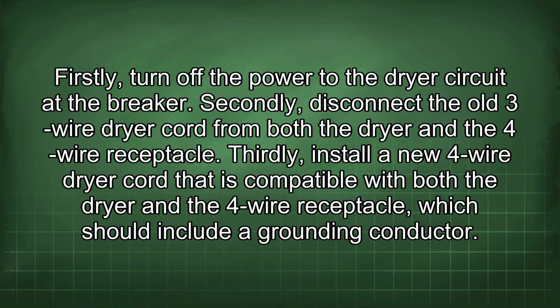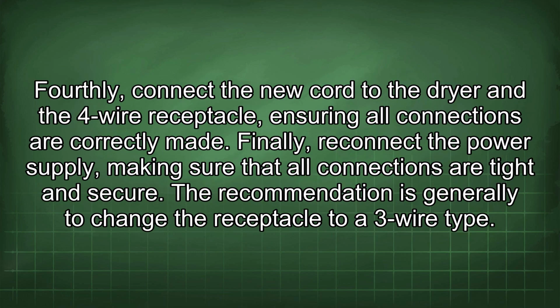Thirdly, install a new 4-wire dryer cord that is compatible with both the dryer and the 4-wire receptacle, which should include a grounding conductor. Fourthly, connect the new cord to the dryer and the 4-wire receptacle, ensuring all connections are correctly made. Finally, reconnect the power supply, making sure that all connections are tight and secure.